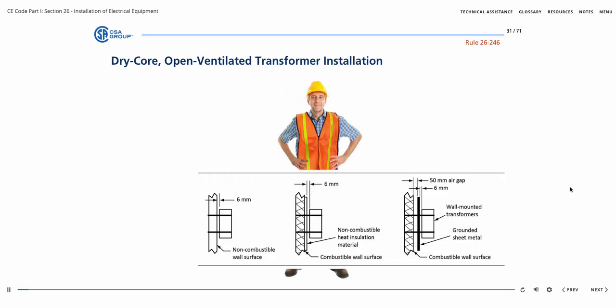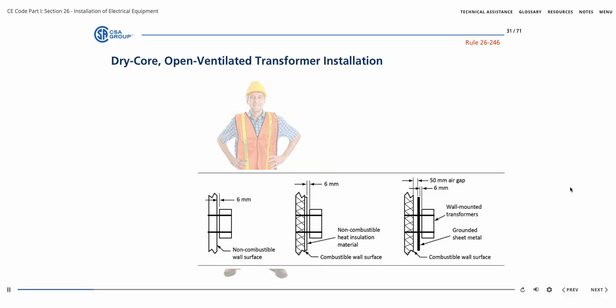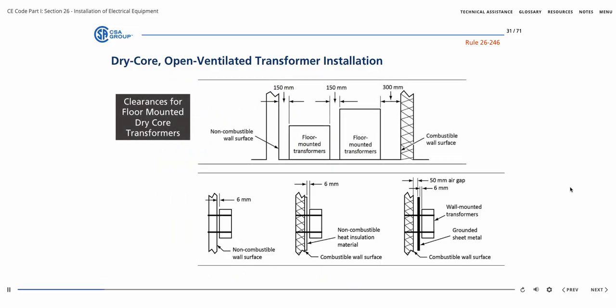Since fully loaded dry core transformers can produce a substantial amount of heat, these types of transformers are not to be mounted too close together or to surrounding surfaces, which can overheat both the transformers and the surrounding combustible surfaces. See both diagrams on the screen.